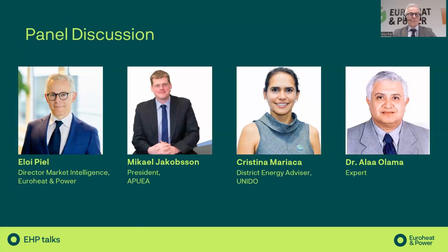Mr. Alao, do you want to react to this? Yes, thank you very much. In their excellent presentation, Alexander and Upasana talked about cooling as a service and explained what it is and what it's for. I agree that it's not a threat or an alternative to district cooling, because district cooling is basically the best solution for high density, high EFLH figures that exist anywhere. So if you have a high density cooling load demand and a high equivalent full load hours, then district cooling is the best solution. But on the other hand, cooling as a service has one advantage that could eventually be incorporated into district cooling.